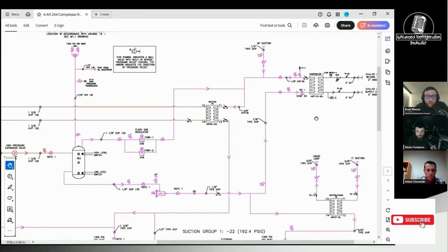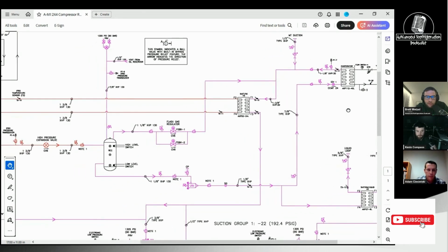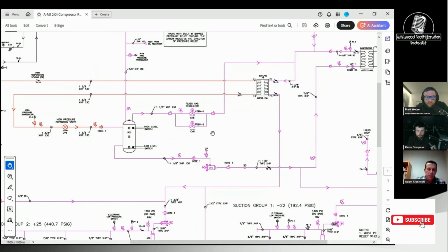Is just one redundant, or do you need that for capacity's sake? In this situation, we did need this for capacity, and it does give you a bit of redundancy, but these valves, the Copeland valves, from a capacity standpoint, one valve was just a little bit too small for the capacity of the unit. Okay. It was enough for the high pressure, but the flash gas, it did need two in parallel.